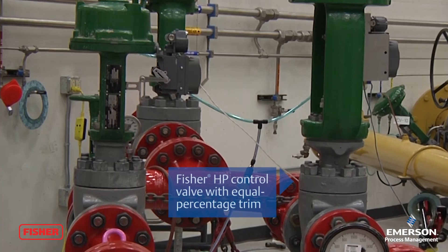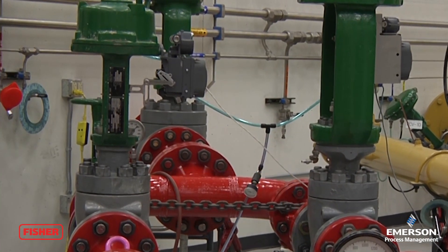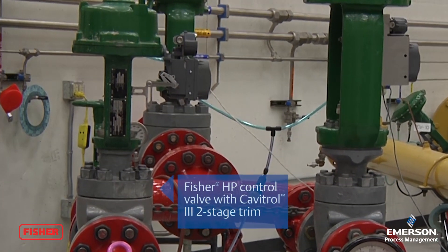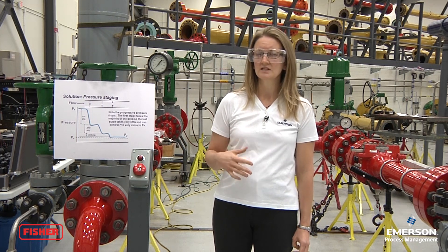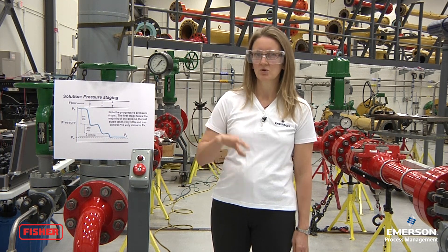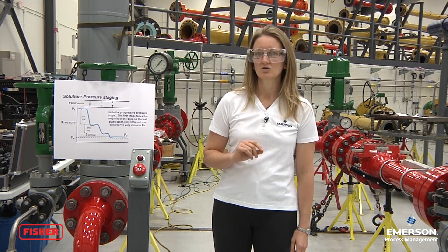So in this next demonstration, we're going to show you the difference between a standard high-pressure product running with an equal percentage trim versus a high-pressure product with a Cavitrol III two-stage trim. We'll be running at about 1,500 psi inlet pressure and about 150 psi outlet pressure. In the standard product, that vena contracta pressure will be below the vapor pressure, and you'll see quite a bit more noise and vibration occurring in the standard product as opposed to the Cavitrol controlled product.